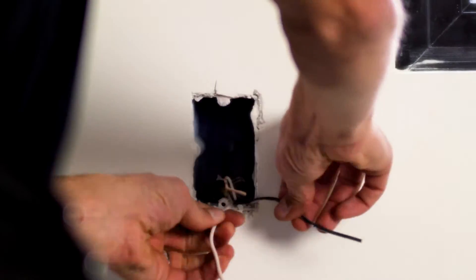I'm pulling out my number 12 Romex cable with three conductors: hot, neutral, and ground. I'm stripping to about seven-eighths of an inch. I'm putting that twist on the end for wrapping around the screws.